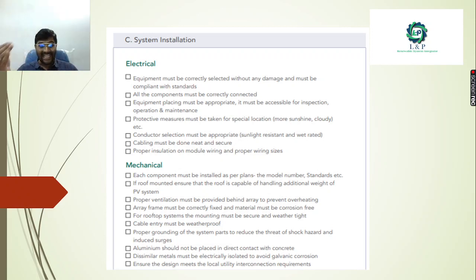On the electrical side, you need to make sure the cabling is proper, insulation is proper, conductor selection has been proper, protection measures have been made proper. The same thing we need to follow for the mechanical things also. And most importantly, you should not connect your aluminum in direct contact with the concrete. Make sure the proper grounding has been done, and make sure your cable entry is weatherproof.